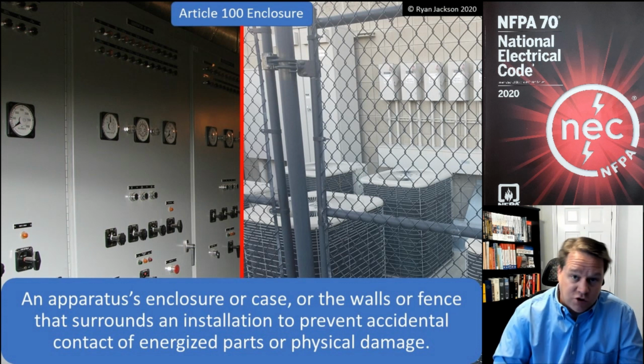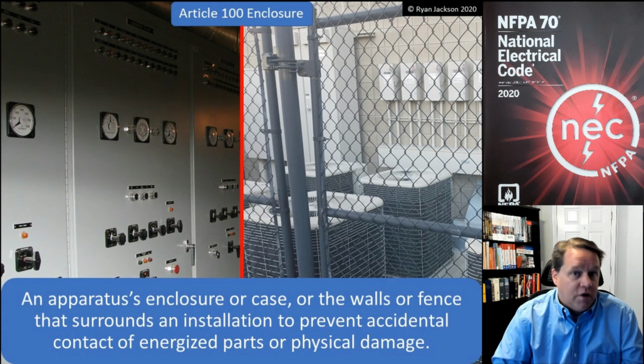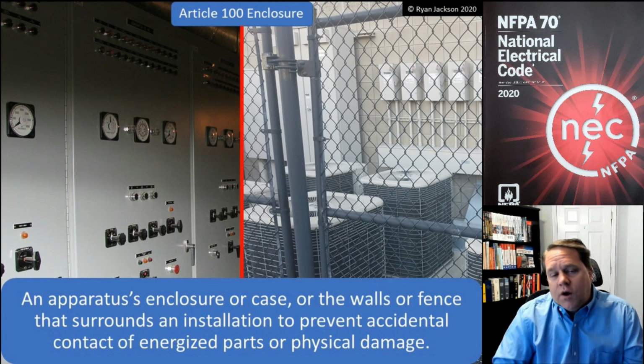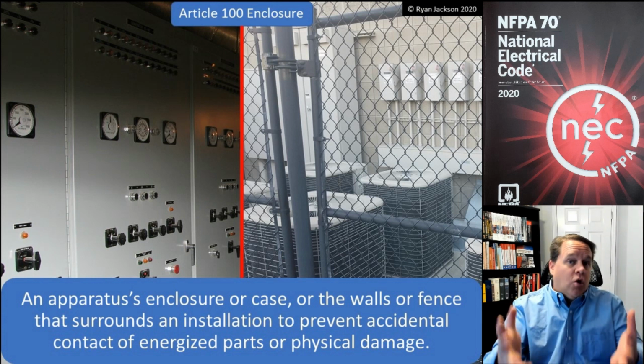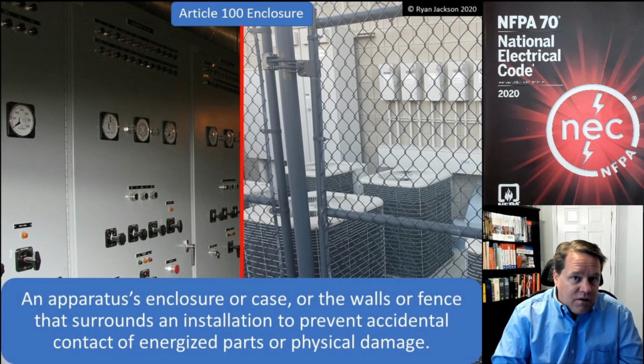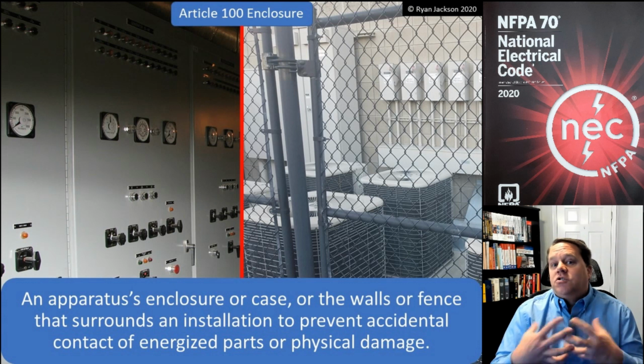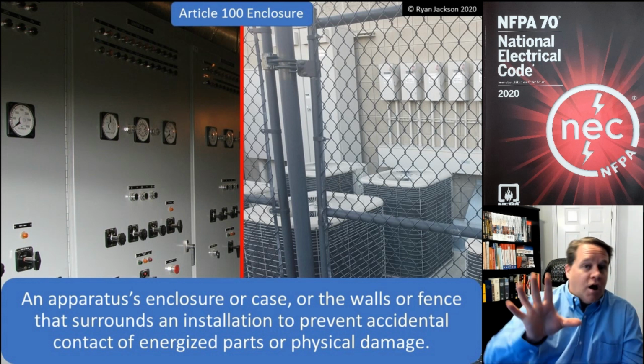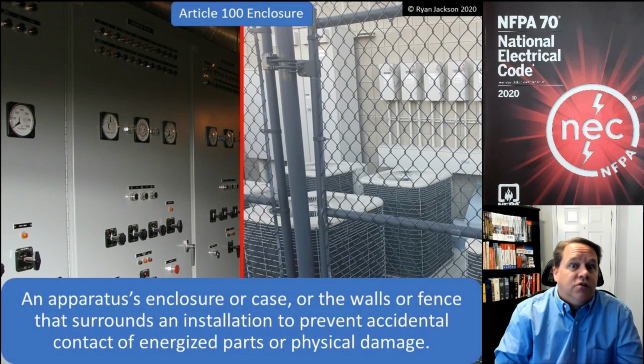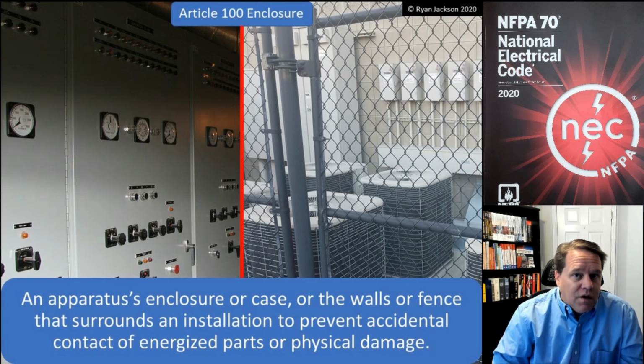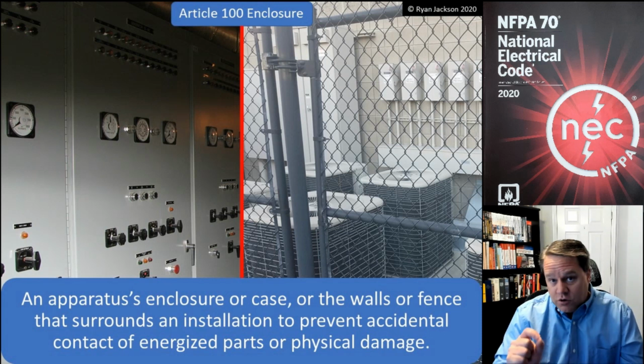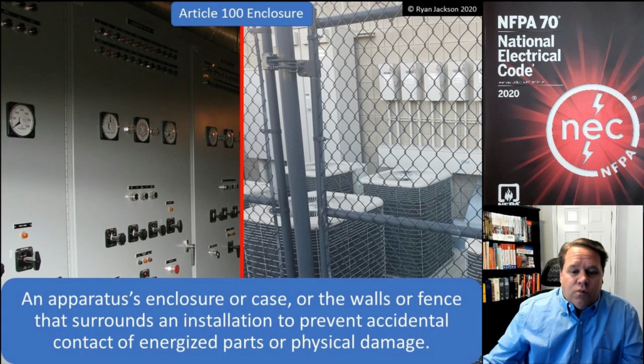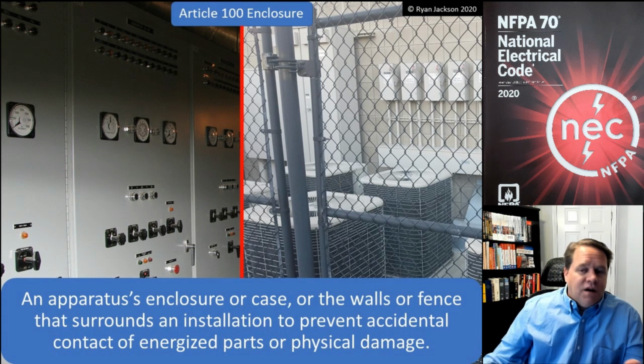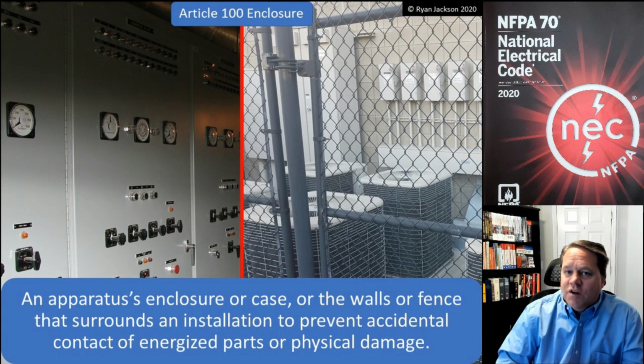And sometimes in commercial buildings, especially older ones or very large ones, you'll walk into an equipment room and you'll have an open transformer sitting there that's not in what we would traditionally call an enclosure. You can walk right up to it and touch it and get yourself killed. However, it's still probably enclosed by the fact that it's what? It's enclosed by walls. So enclosure is a much more broad definition than you might originally think.